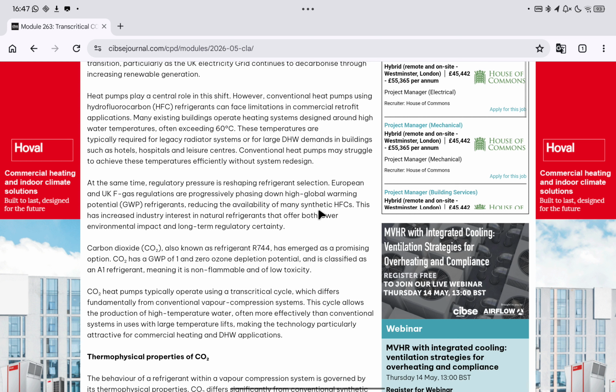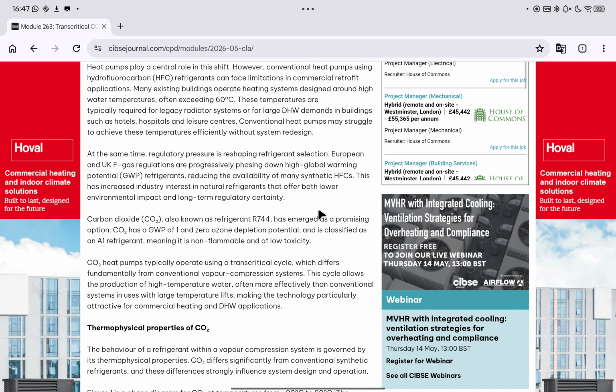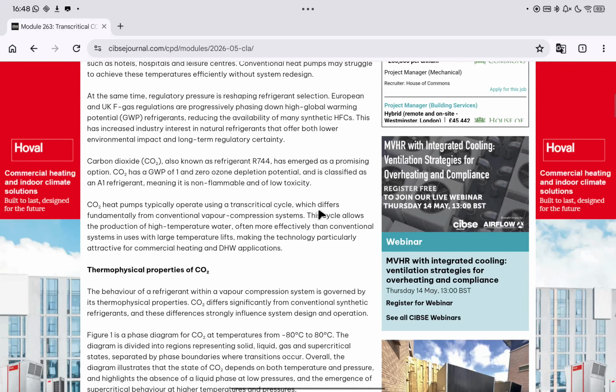CO₂ has a GWP of 1 and 0 ozone depleting potential, or ODP, and is classified as an A1 refrigerant, meaning it is non-flammable and of low toxicity. CO₂ heat pumps typically operate using a transcritical cycle, which differs fundamentally from a conventional vapor compression cycle system. This cycle allows the production of high-temperature water, often more effectively than conventional systems in uses with large temperature lifts, making the technology particularly attractive for commercial heating and domestic hot water service applications.